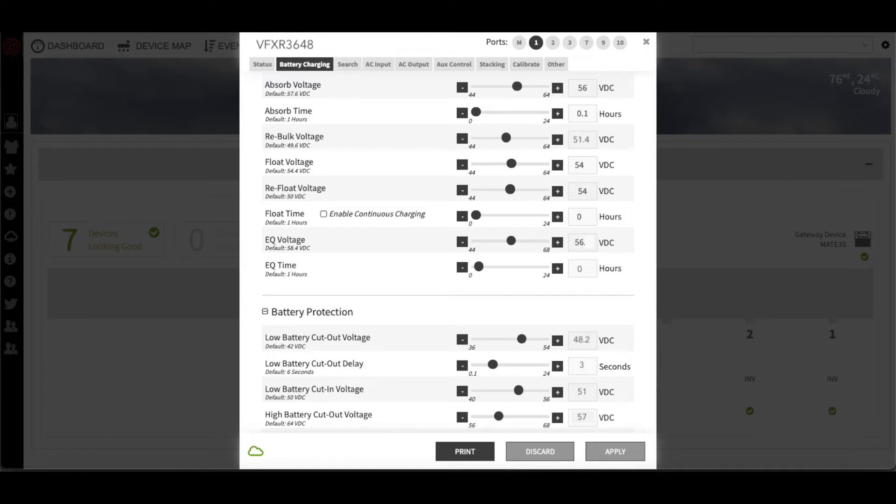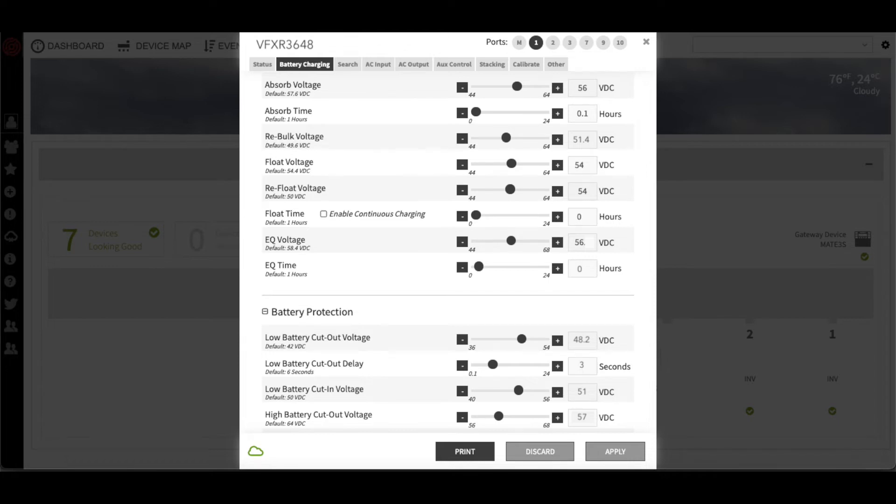On the battery charging tab, we will make sure that the absorb voltage is 56 volts, the absorb time is 1 tenth of an hour, float and equalization time should both be set to 0 hours, and equalization voltage should be roughly equal to the absorb voltage.